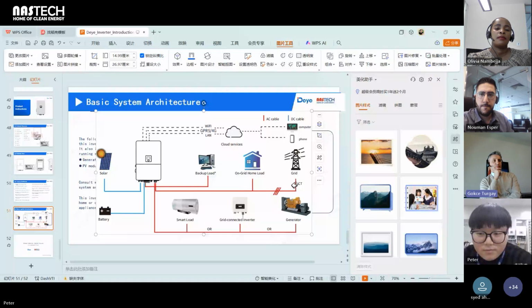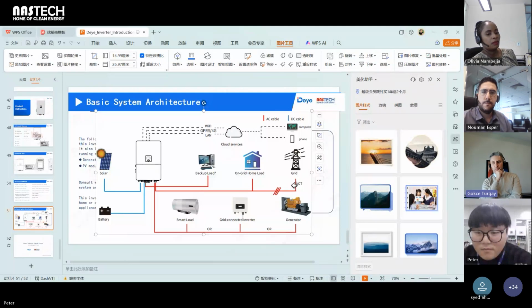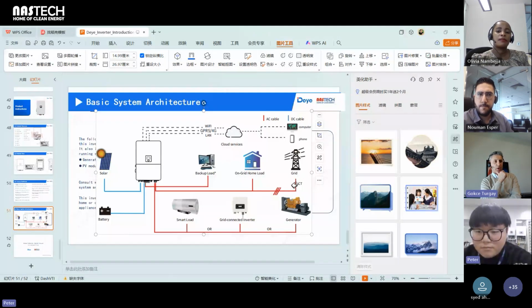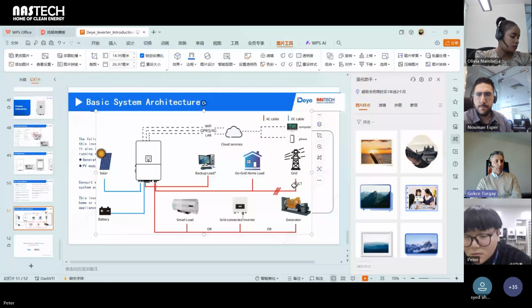Another one, what is the minimum number of batteries that can be installed with a 50 kilo inverter? So that would be 4 pieces, if it's a BOS-G, which is 20 kilowatt hour minimum. And the maximum will be, I think, 16 in series, which is 80 plus kilowatt hour. Can hybrid inverters be connected with on-grid inverters? That I think we already answered that question.